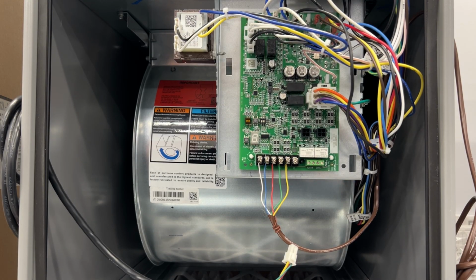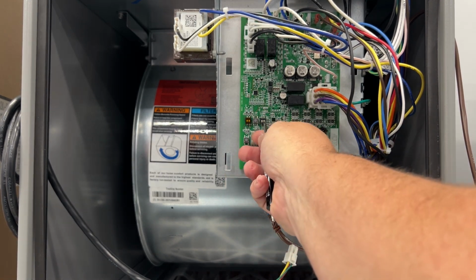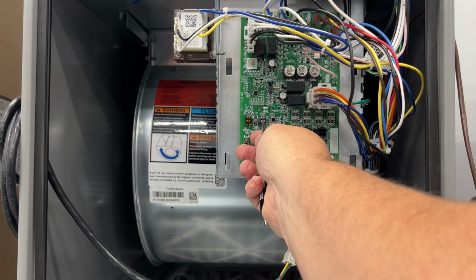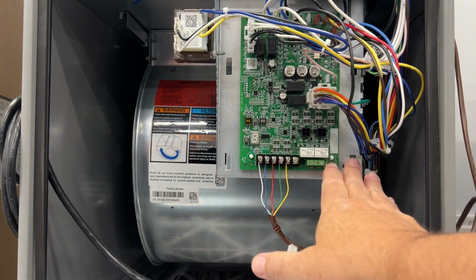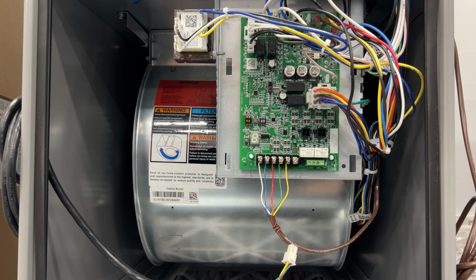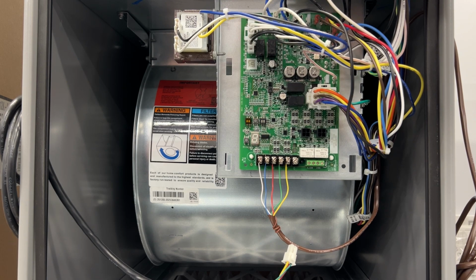Now, what if you have this furnace going into a certain situation where you're just replacing the furnace and not the outdoor and indoor unit, say on a 410A system? In that case, all you'll need to do is push both these dip switches up to disable. That tells the system that you don't have a need for RDS or refrigerant detection. And so when it comes on this time, it's just going to bypass the purge and go right into normal operation.